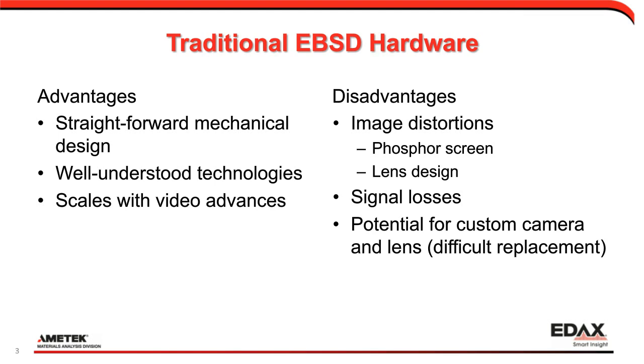The general advantages of traditional hardware are a straightforward mechanical and optical design using well-understood technologies, and the ability to scale with video advances by swapping the sensor in the back — the front half of the design remains nearly identical. The disadvantages include image distortions from the phosphor screen and lenses, signal losses at each stage of image transfer, and potentially prohibitive cost to upgrade cameras depending on how customized the design is.